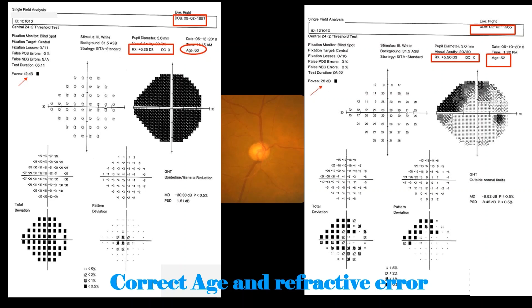As threshold values are compared with age-matched normative values, incorrect age entry will lead to comparison with the wrong set of normal values. Also, failure to properly correct the refractive error will cause stimuli to defocus and blur resulting in improper test results.